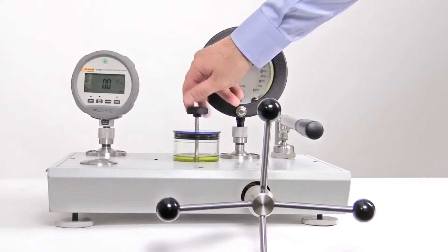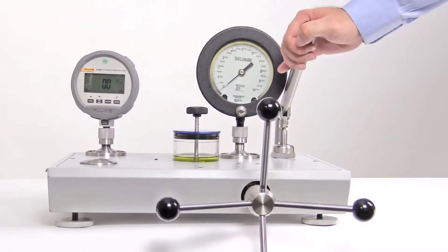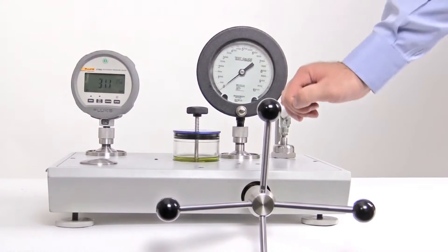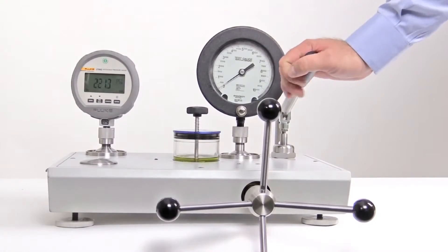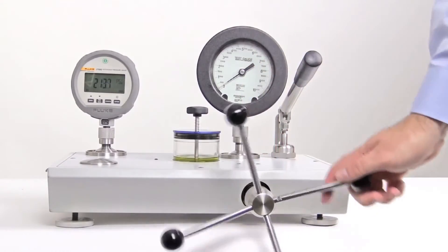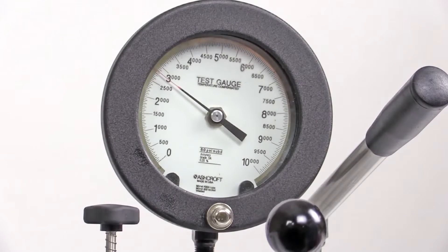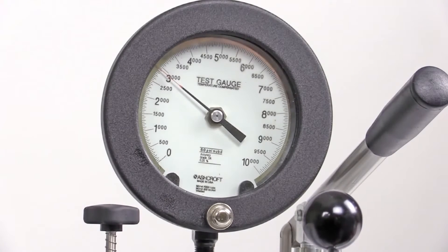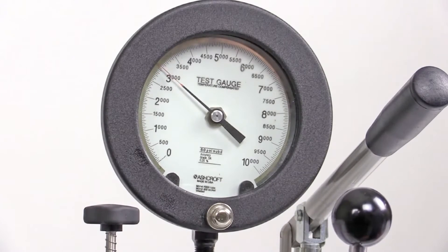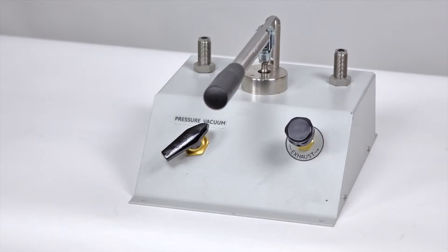To generate pressure, simply close the reservoir valve and use the screw pump to increase the pressure. The screw pump has a fine pitch thread allowing for fine-tuning of pressures. Use the P5510 when you need to generate vacuum to 2 MPa or 300 psi.